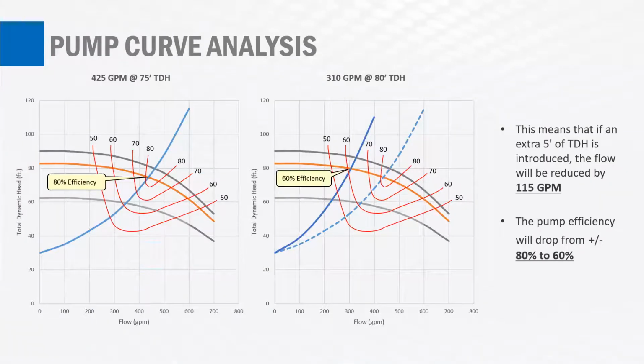So at this time, I'd like to take a closer look at pump curves. And what do these really mean? What's going on here? You can see on the left, this particular pump curve that you see in red is a 425 gallon per minute at 75 total dynamic head situation. And the way that we determine that is with the blue curve, that's what the system pressure is at that flow.